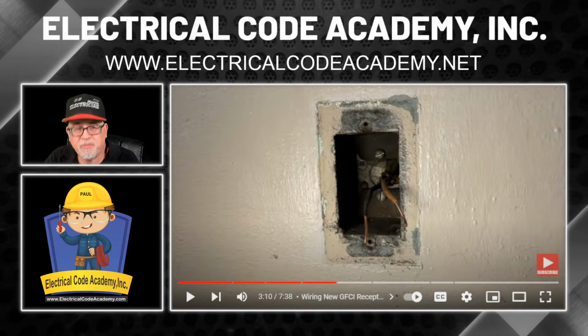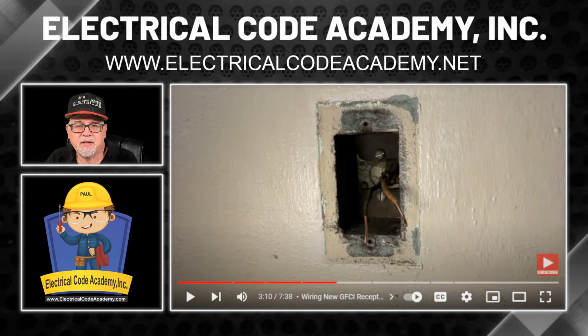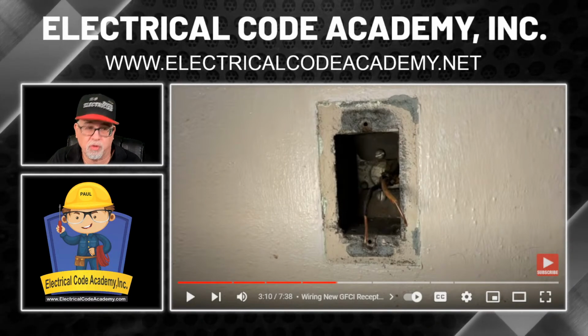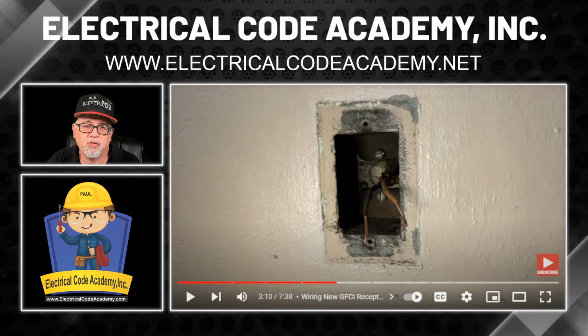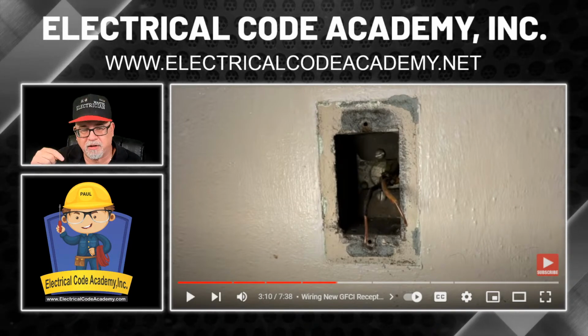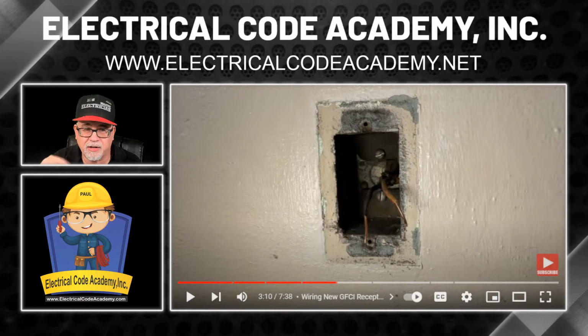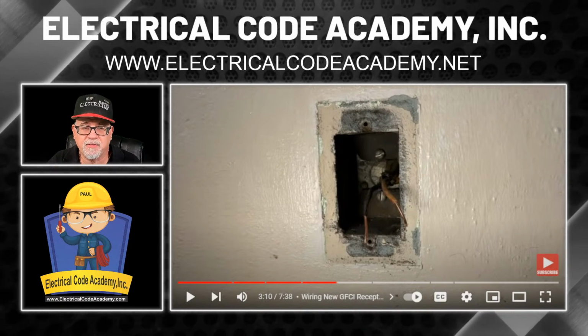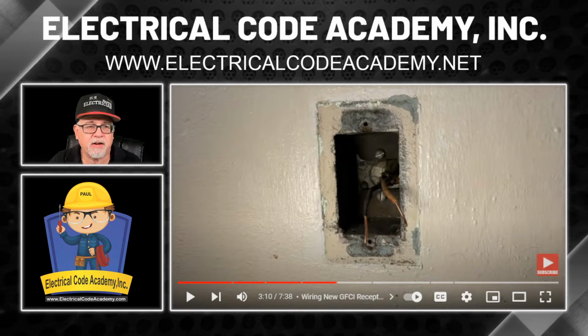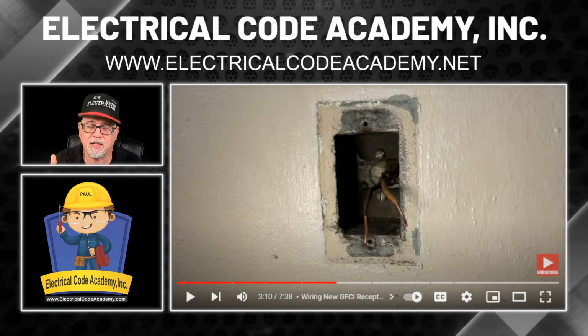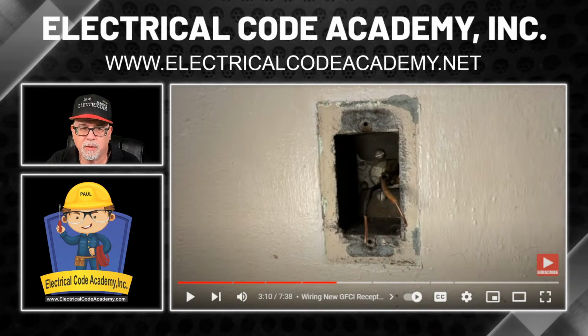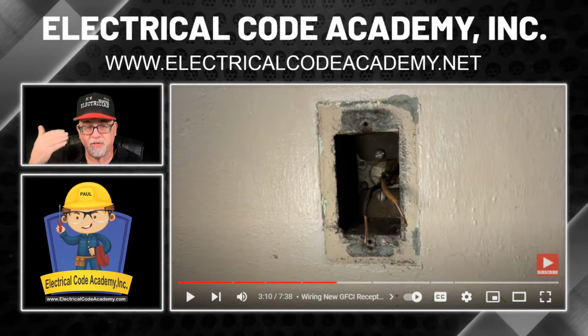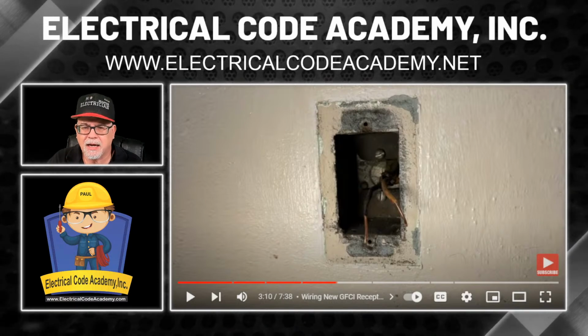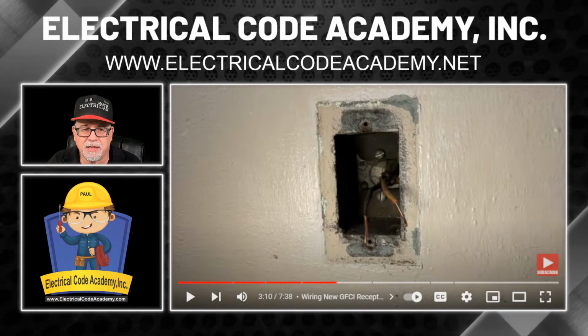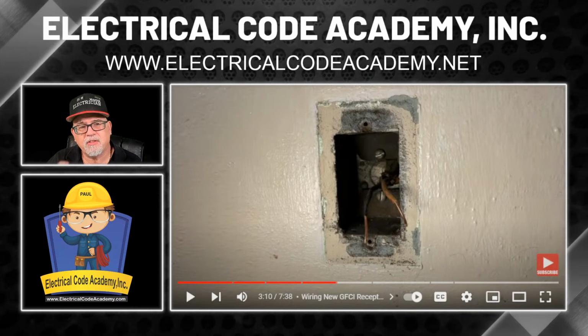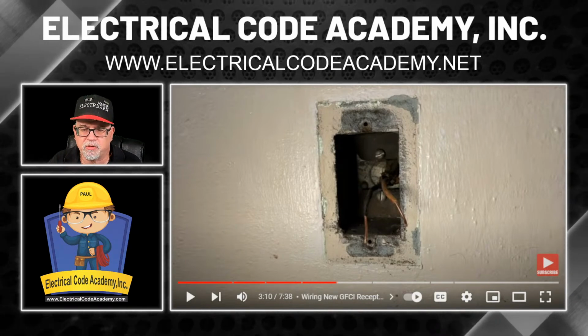Now, MC cable, metal clad cable, doesn't have the armor used on traditional MC, doesn't use the armor as an equipment ground. You have an equipment ground inside the cable, right? Either green insulated or bare. It doesn't matter. UL 1569 doesn't care. Most manufacturers with this smaller branch style MC will put an insulated green equipment ground. As it starts getting larger into feeder size MC, it tends to become bare. But the code allows for it. Not a problem either way. But the big issue is the armor on MC cable is not to be used as an equipment ground.